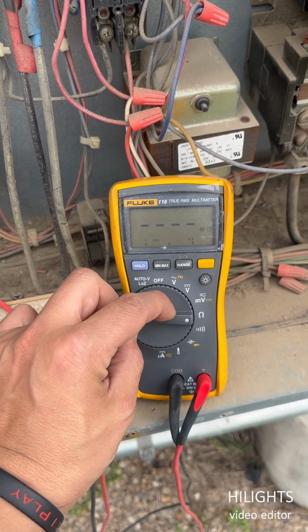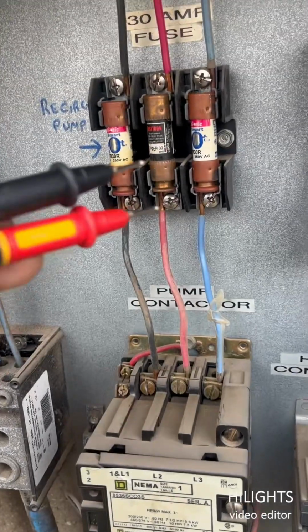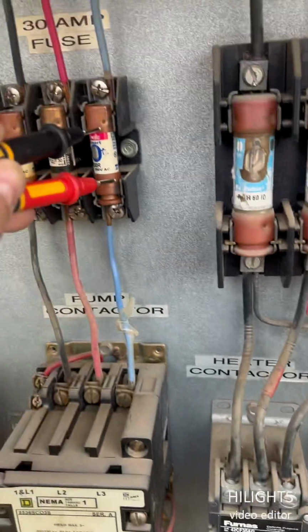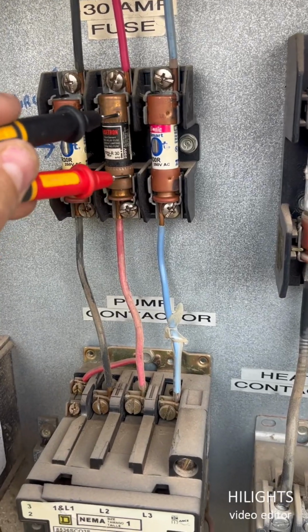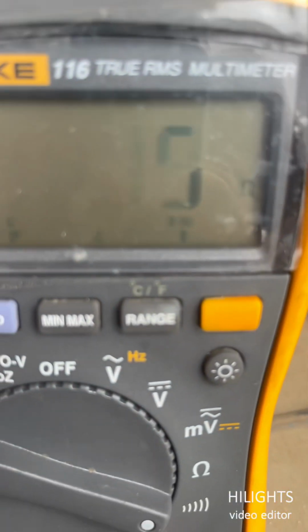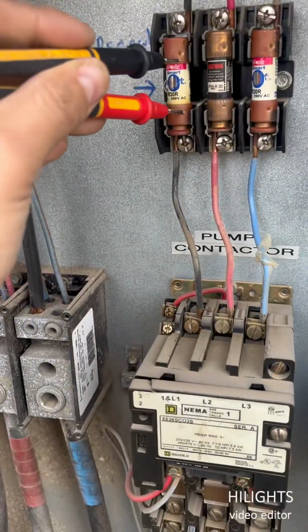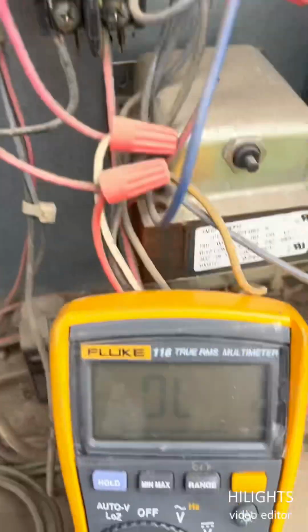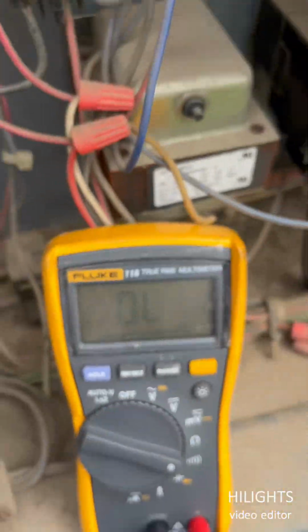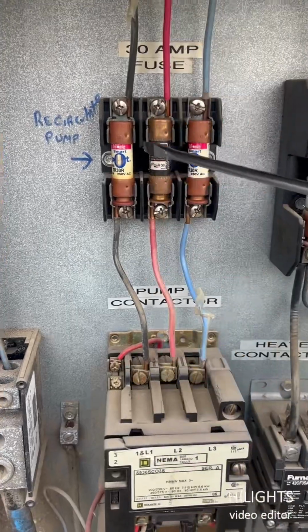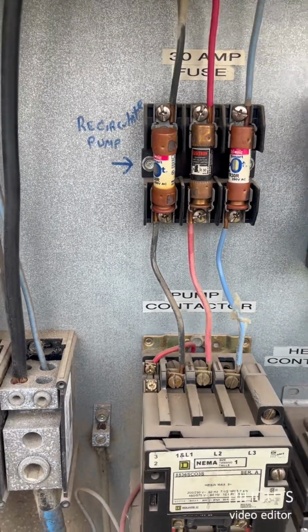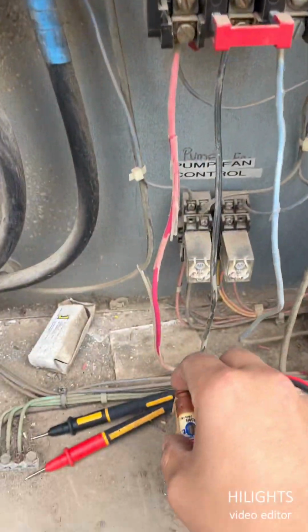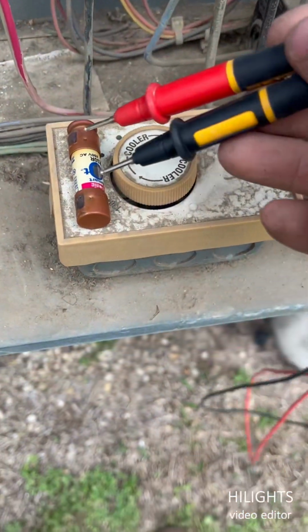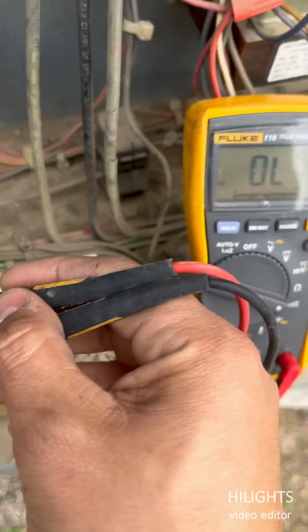Alright, let's put it on continuity. We're gonna check the continuity between the fuses. Remember, if it beeps, it's good. That means you have continuity. Beeping. And beeping. Those two are good. The last one, no beeping. Oh well, open line. That means that fuse is bad. Alright, let's pop her out. Let's just check it one more time, just to be sure. And yep, open. Bad fuse.